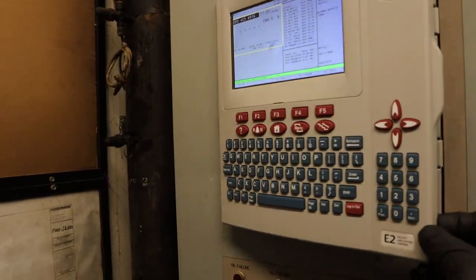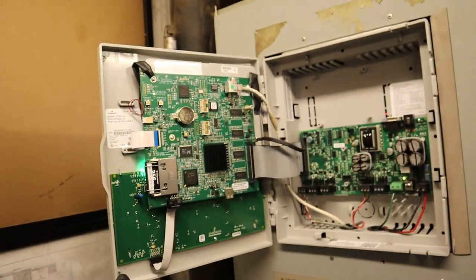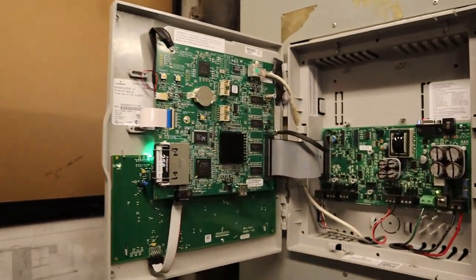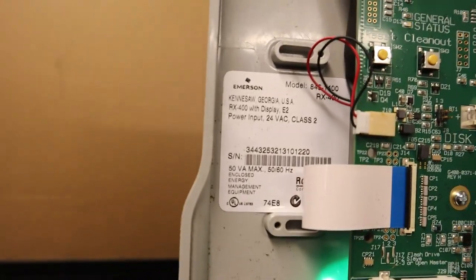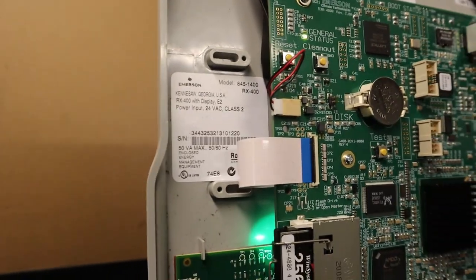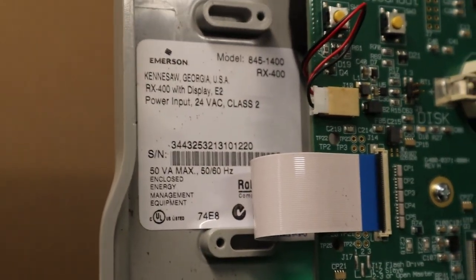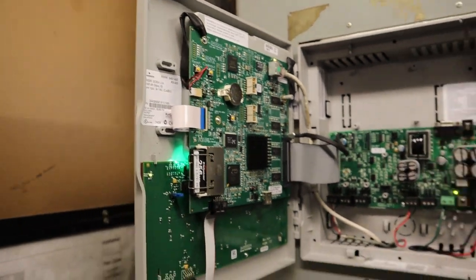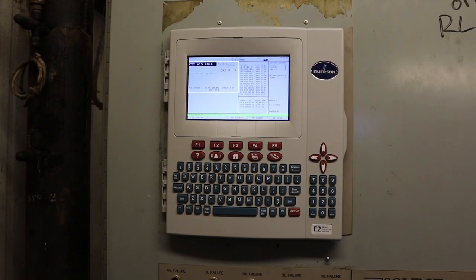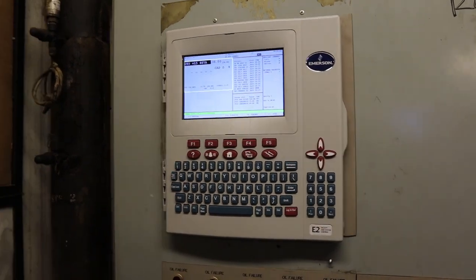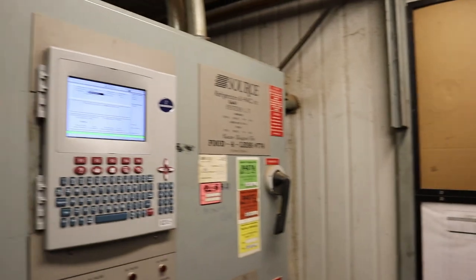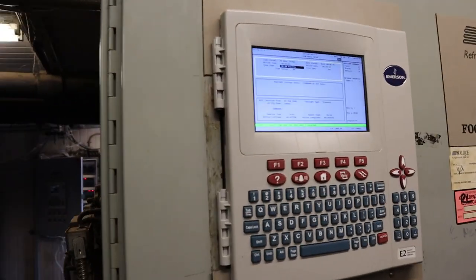So now just teaching the new generation to do these controllers, program them, install them. So everything is back online. No alarms. Brand new RX 400. Communication is good. The only thing I didn't record was I actually put it in the ethernet network and then put them in the group name. So they have to be in the same group name to communicate. But we did all that. We called Emerson, they were able to communicate and look up the controllers. So we're good.